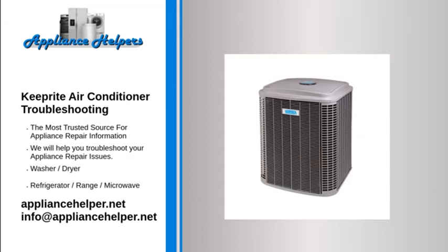AC unit is not the correct size. An AC unit that is too small will have continuous run cycles. An AC unit that is too big will have short run cycles. Both of these issues will eventually cause your HVAC system to prematurely fail. Confirm you are using a unit that is the appropriate size for the space you are cooling by contacting an HVAC professional. Outside compressor condenser unit is obstructed.